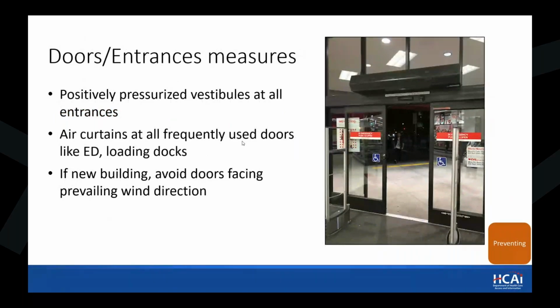Particular focus at doors and entryway locations: positive pressurization, including the addition of vestibules or other space-planning measures to break the dependence on the door leading directly into the clinical space, is really important. Utilizing air curtains, which are fairly typical for areas already like emergency departments and loading docks.